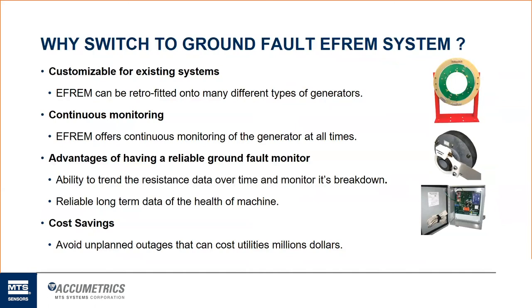It gives you that continuous monitoring at all times of the generator. Some of the advantages are that ability to trend that data over time, so they can monitor for that breakdown. On their traditional systems, it's literally just a go, no go. You know, that old brush actuator style, they may contact and take a measurement one day and it's fine. The next day you come in, you've got a ground fault. You have no sense of predictability of knowing when that may occur. Do you know if you're at 15K ohms one morning and you're very close to that 10K threshold, and you come in the next day and all of a sudden you've got a ground fault and everybody starts panicking, shut the unit down, and get some repair done. So that's the biggest advantage, is just that ability to monitor it over time, reliable, long-term, healthier machine.